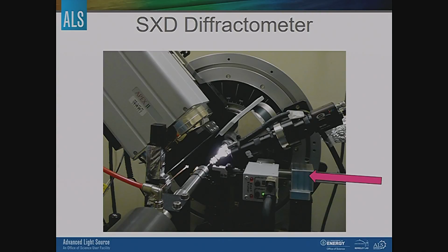Other important things in a single crystal experiment. Well, duh, X-ray beam, right? Comes in this case from the right, goes through, there's a beam stop to keep it from hitting the detector. We have a timing shutter, which is actually becoming a thing of the past. This may or may not be pertinent to you, but most systems in the next couple of years will be progressing to shutterless data collection and no more timing shutters, because we'll have CMOS detectors instead of CCD, which don't require dark time to process the images. So this is actually out of date as far as the beamline that I took this picture. They don't have that anymore.